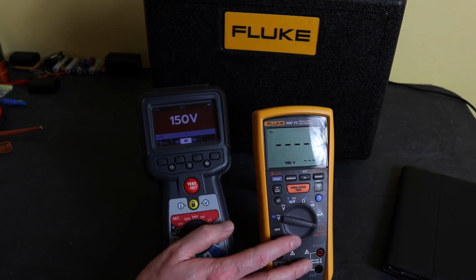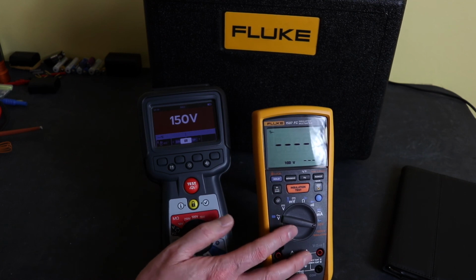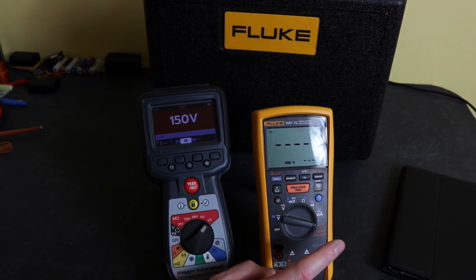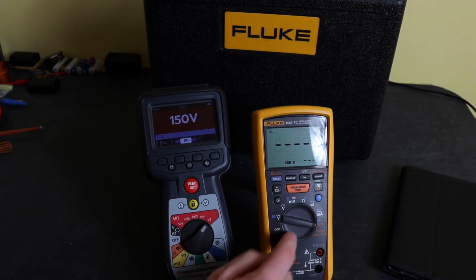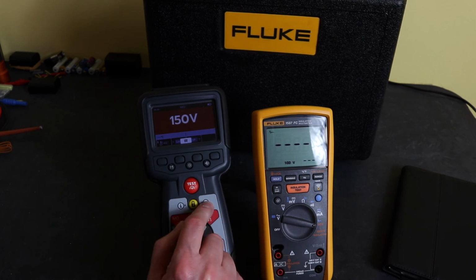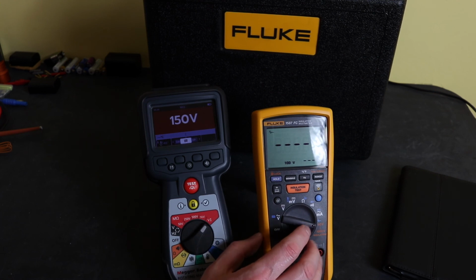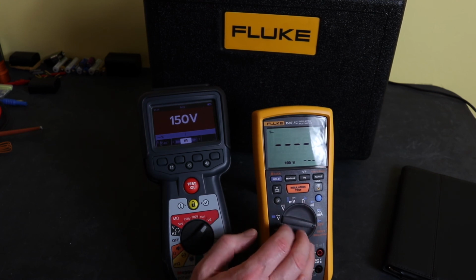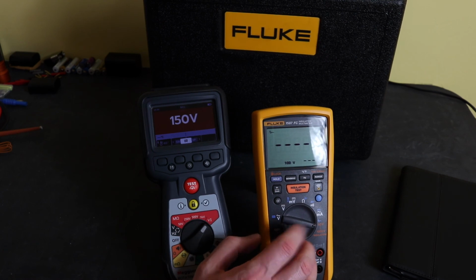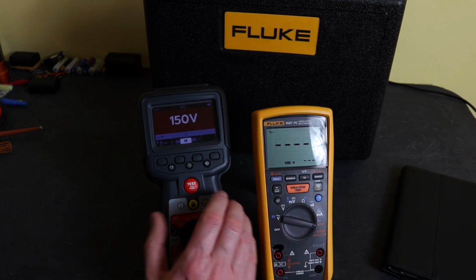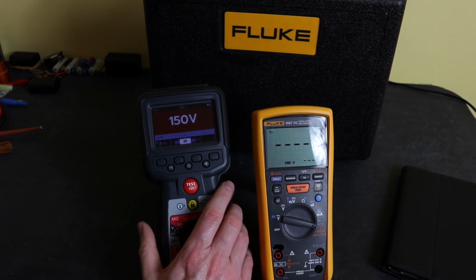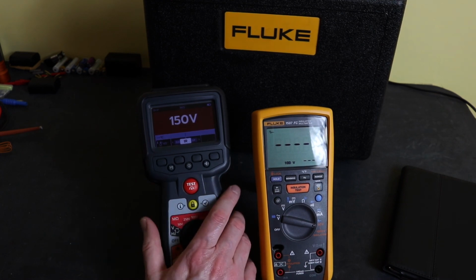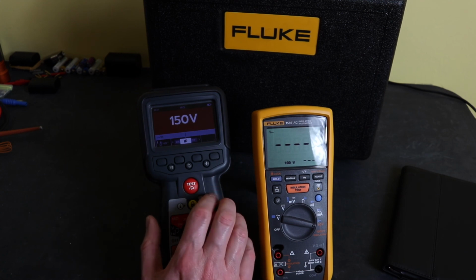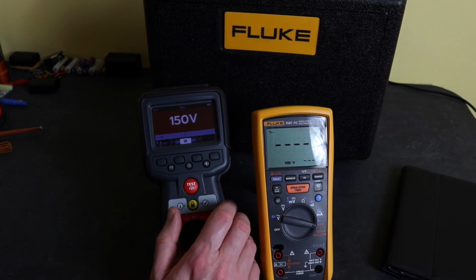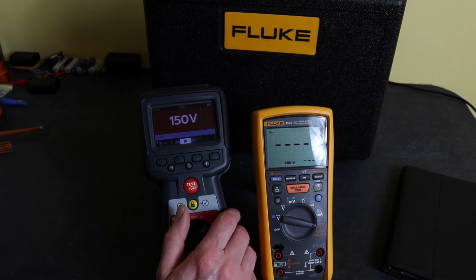So for me, this instrument is aimed perhaps more at a controls technician who wants the voltage and the current capability measurements. It's quite good for measuring transducers, 4 to 20 milliamp, and it does the job much better than the MTR105 does here. So yeah, a controls technician wants that functionality and perhaps a little bit of insulation testing on the side, more as a go-no-go testing to say that something is safe to energise, rather than something like the MTR105 here that is much better for diagnostic testing and long-term trending of data for preventive maintenance on motors, which is the field that I'm in more than a control and instrumentation side, really.